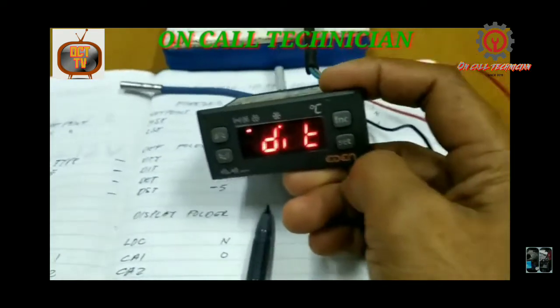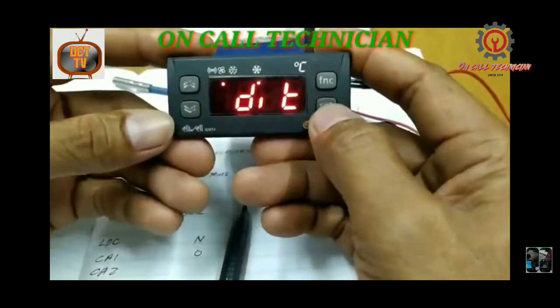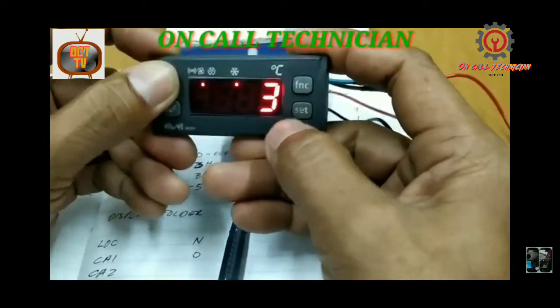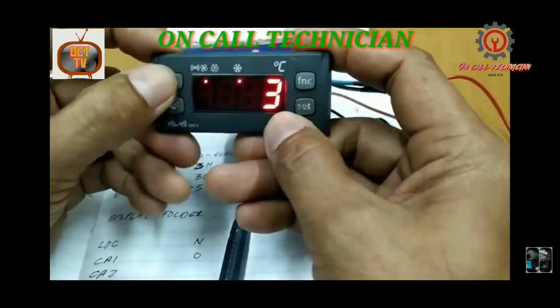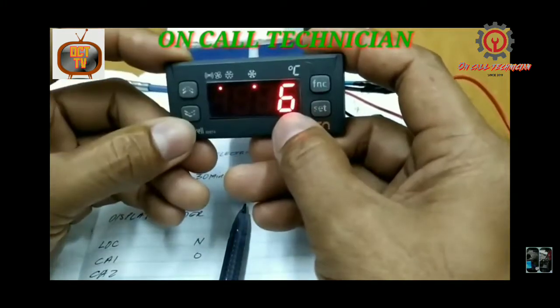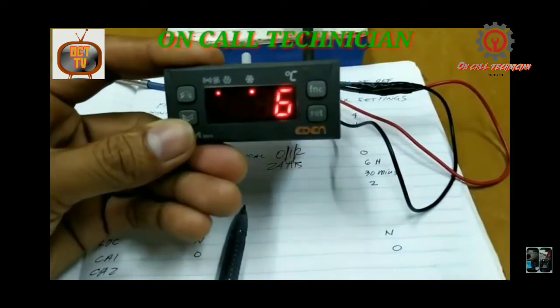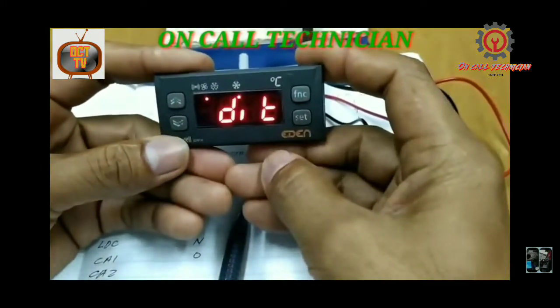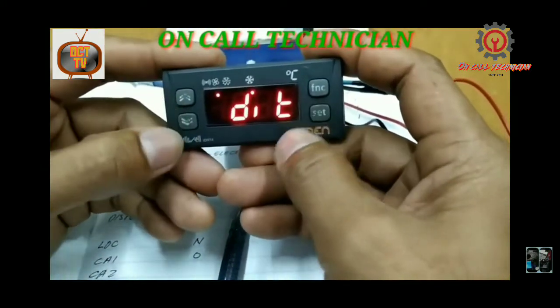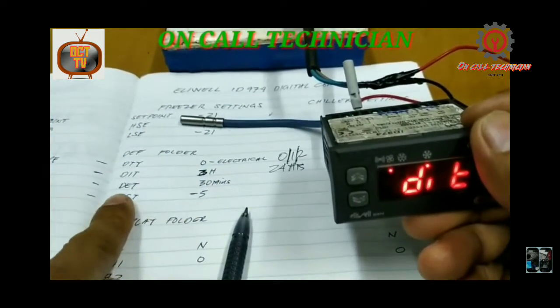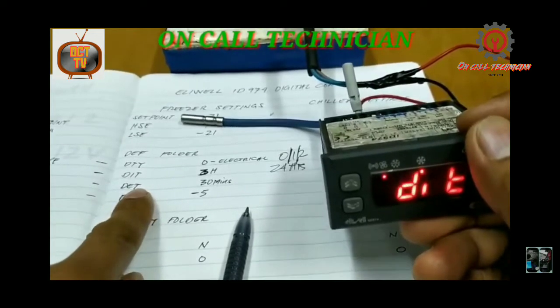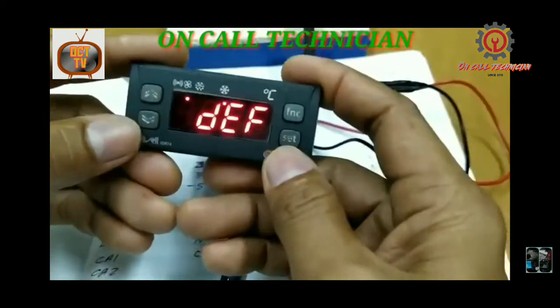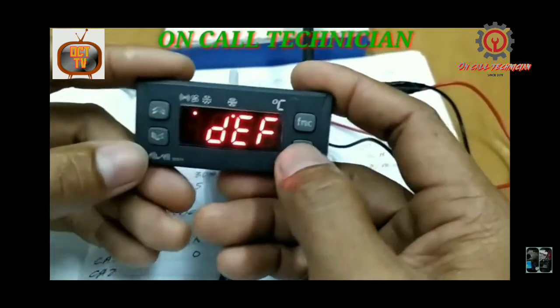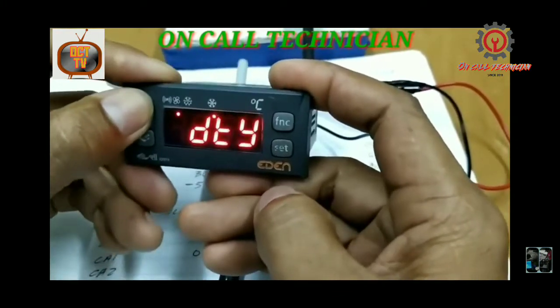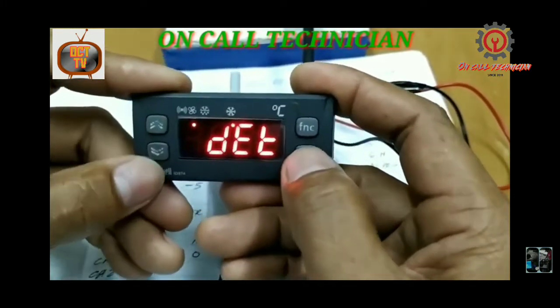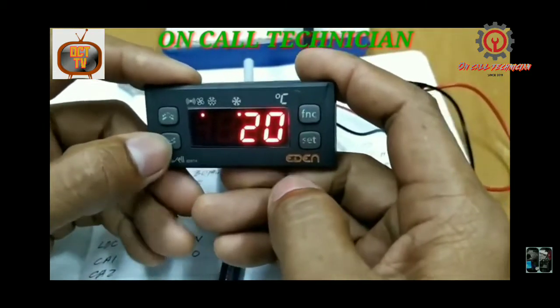Okay, so the operation is in hot gas. Okay, next is DIT. Okay, the DIT is programmed to 3 hours. Okay, the value is 2. Okay, there, 3. So let's change that to 6. Okay, because we are in a chiller mode. Okay, 6. So every 6 hours the chiller will defrost. Okay, so next, guys, let's proceed to DET. Okay, the DET is the defrost duration, and the default here, guys, is 30 minutes. Okay, again, defrost, press this button, and let's locate the data, DET. Okay, press set to reveal the value, and the value is 20 minutes.